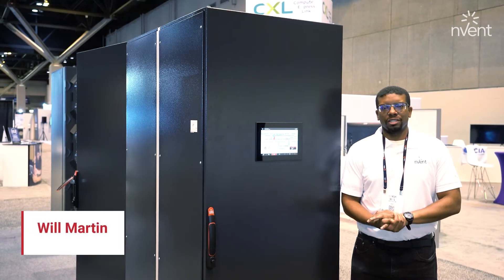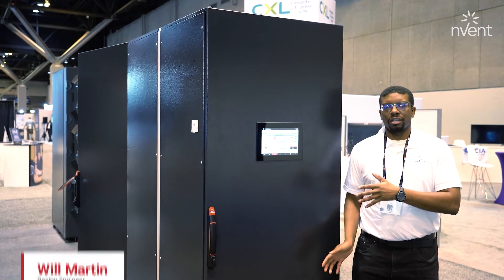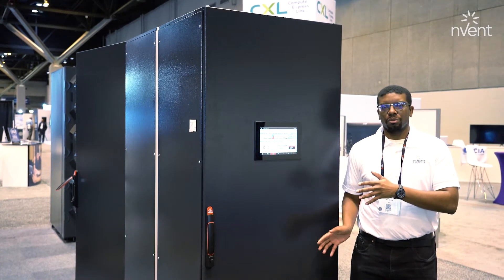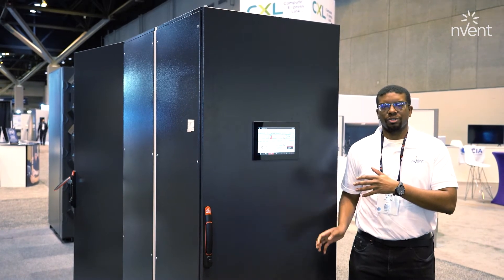Hello, I'm Will Martin, a design engineer with nVent Hoffman, and this is our Rack Chiller CDU 800. This unit has 800 kW of cooling capacity at a 4k approach, and it provides 950 liters per minute at a 45 psi pressure differential.